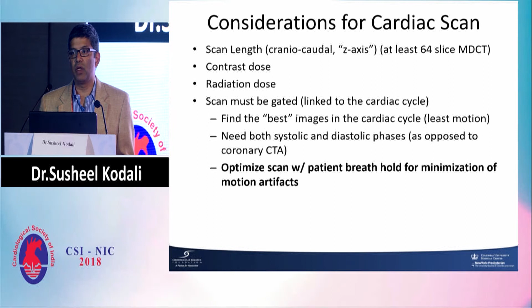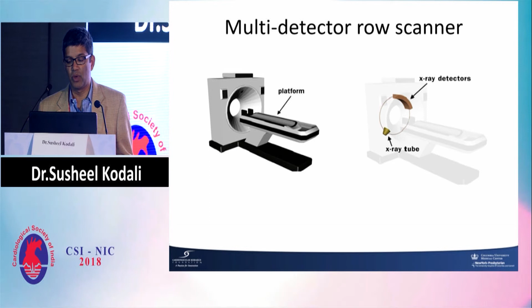I think most of you are familiar with how a CT scanner works, but basically, obviously there's an X-ray tube and there are these detectors. What's really relevant is the detectors. When we talk about 64 slice versus 128 versus 320, that's what's relevant. Because when we're talking about helical scanning, it's continuous. There's lots of overlapping data. The detectors just continue to rotate and the patient moves through the scanner.